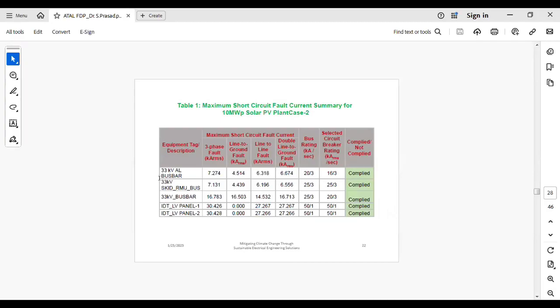What are the different equipments we have considered? A 33 kV aluminum bus bar is there. Skid RMU bus is there. 33 kV bus bar is there. This particular 33 kV bus bar is the point of interconnection. And IDT LV panel 1. There are two LV panels for the IDT transformer, because this is a three winding transformer.